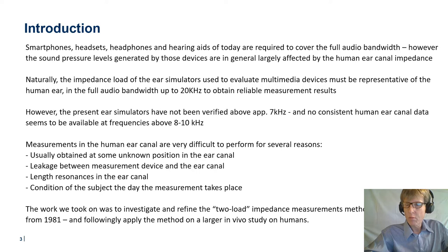The reason for this is that measurements in the human ear canal are very difficult to perform for several reasons. They are usually obtained at some unknown position in the ear canal relative to the eardrum. Often, you see leakage between the measurement device and the ear canal. Length resonance in the ear canal can also easily impact the accuracy. And last but not least, the conditions of the subject on the day the measurement takes place can also play a major role.